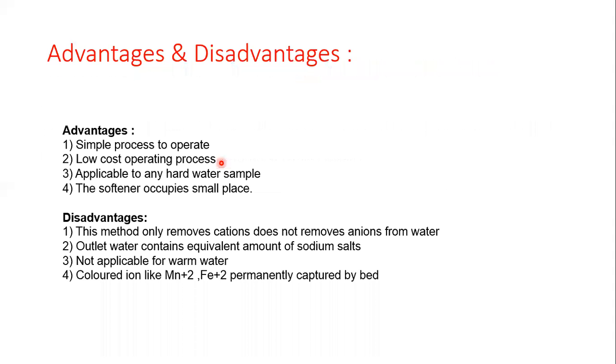Now let us see the advantages and the disadvantages of this method. The advantages: it is a simple process to operate, and a low cost operating process. This is applicable to any hard water sample, and the softener, that means the sodium zeolite bed which we use, occupies a small space.